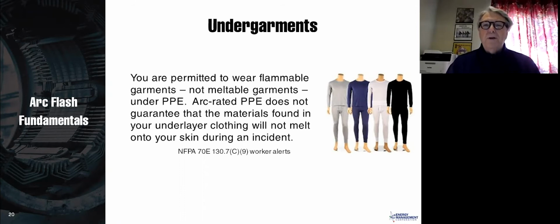You are permitted to wear flammable garments, but you are not permitted to wear meltable garments under your PPE. Arc-rated PPE does not guarantee that the materials found in your underlayer clothing will not melt onto your skin during an incident. So the most common clothing that we typically wear as underwear is made of cotton. And of course, that is flammable, but it is not meltable, and that's perfectly fine.